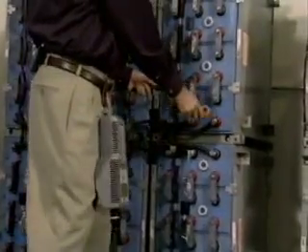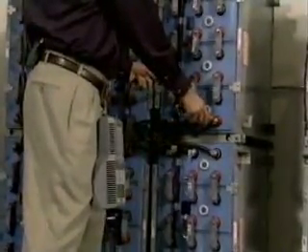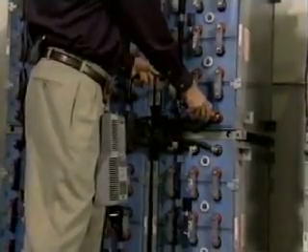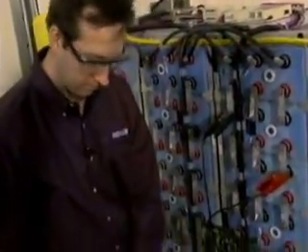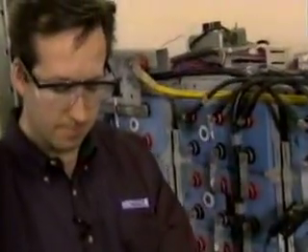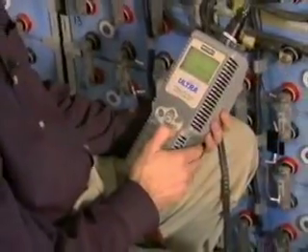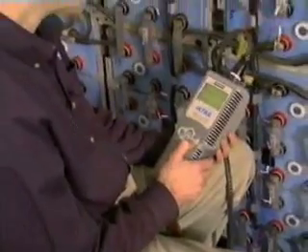But suppose the models you're testing do not match any in the Celltron Ultra database. You can have the analyzer create a reference standard based on the values of the batteries you're actually testing. This value is based on a percentage of batteries that have the highest conductance value. Here's how to set it up.